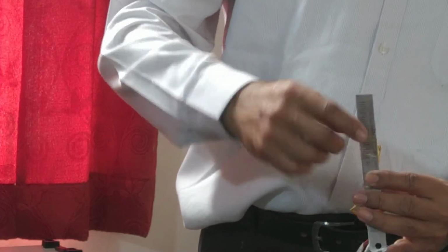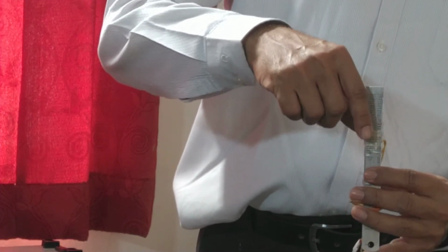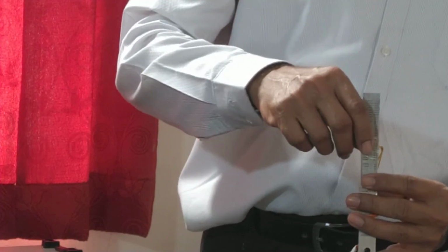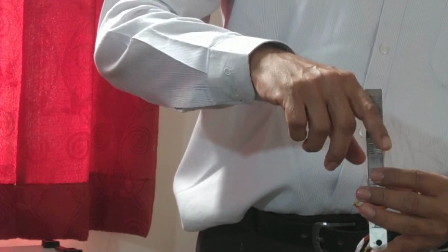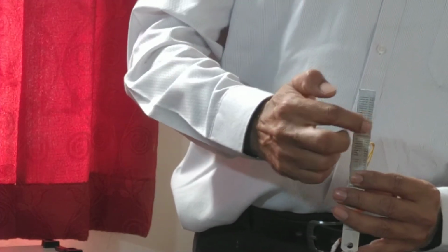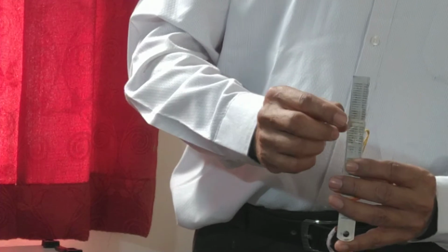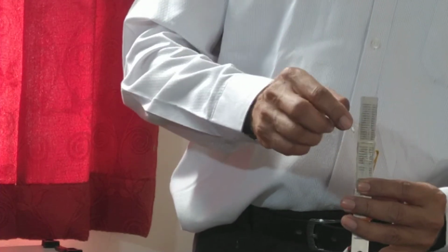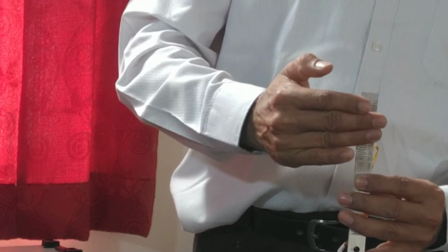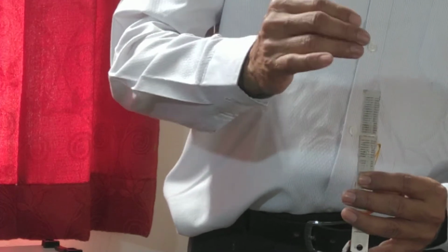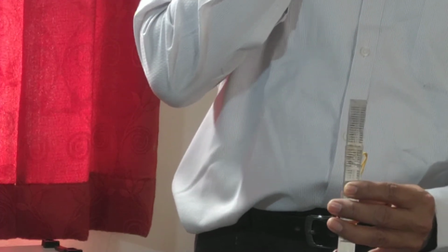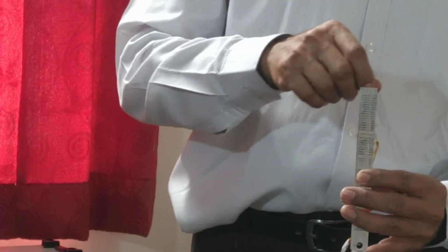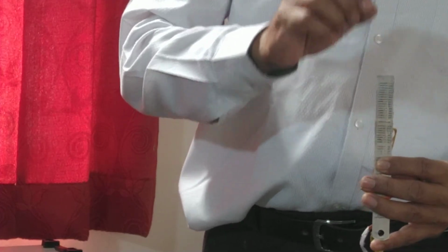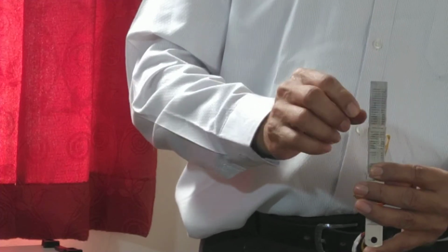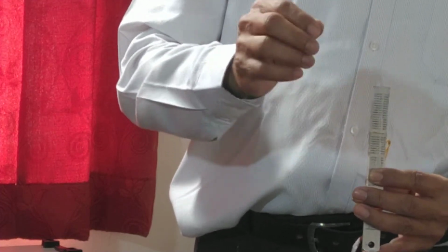The two terminals coming out of the strain gauge are kept away from the adhesive material. The mounted area is then covered using a sellotape, and we use rubber backing material to protect the strain gauge from absorption of moisture. That protection is kept for maybe 4 to 6 hours, after which the strain gauge is ready for usage.